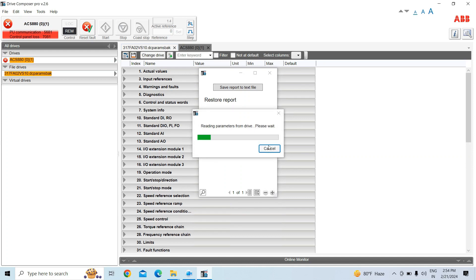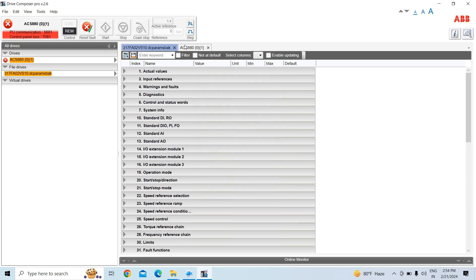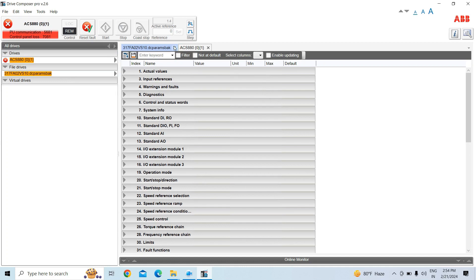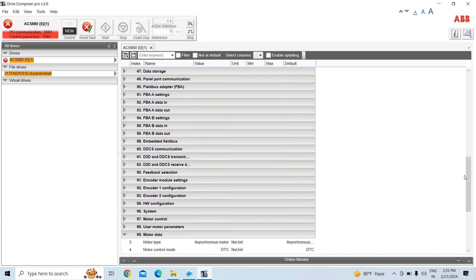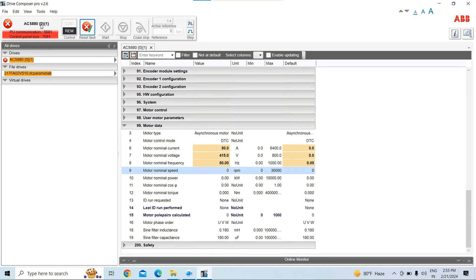Reading parameters from the drive is successful — it has reloaded and read back from the drive. Now I am closing the open file that we saved earlier. In parameter group 99, you can see the parameters have changed. This confirms that the backup was taken, the parameter was changed offline, and reloaded to the drive successfully.